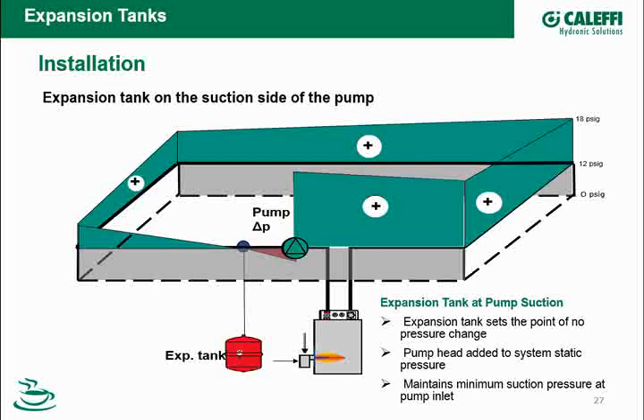Okay? That does a couple of things for me. First off, it ensures that my system always sees, as a minimum, the static pressure of the system, something that I've calculated and want to see. So I'm not going to run into any kind of pressure problems. In fact, with the exception of getting close to the inlet of that pump, the head pressure is going to be additive all the way around to the static pressure of the system. So it's actually going to give me a little more safety margin on the limits of my system.